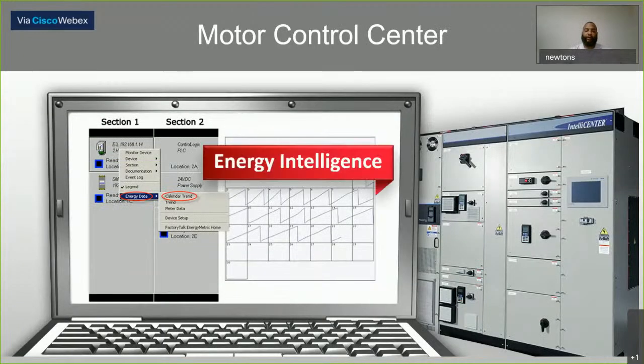So what type of information can we pull from that? Well, one, using the IntelliCenter software, through the use of a clean HMI that's mounted on the IntelliCenter, you can easily trend your power usage, look at your energy data. You have access to your event log. How many trips have you had on which motor? What time did it happen? And from there, you can take that information and say, hey, was it caused by a storm? Was it caused by a machine next to it, upstream, etc. So that's really where the beauty comes in, using an IntelliCenter, pulling in these diagnostics, because if you're not pulling this information in over a network, you're missing out on a lot of capabilities of these smart devices that are ready for you to use.